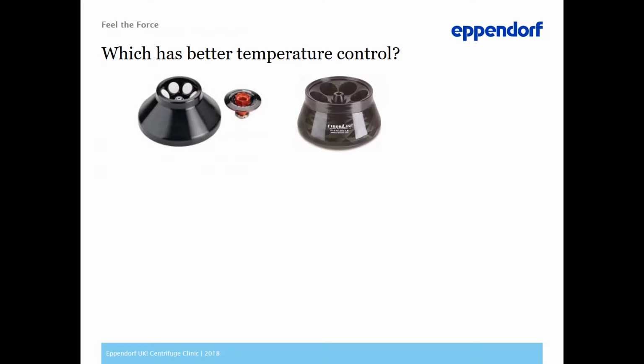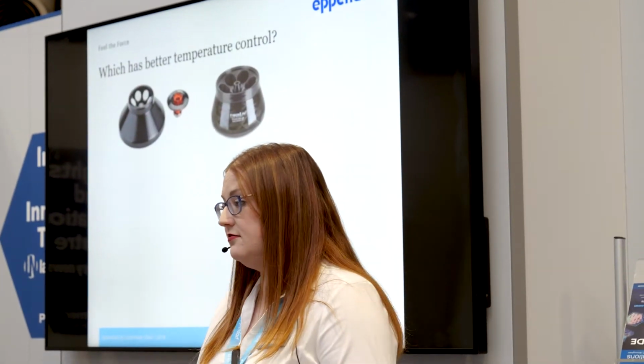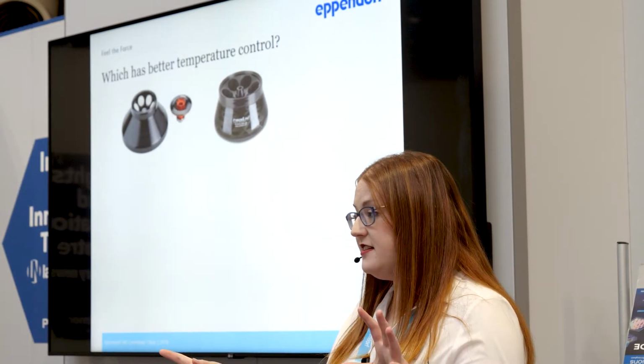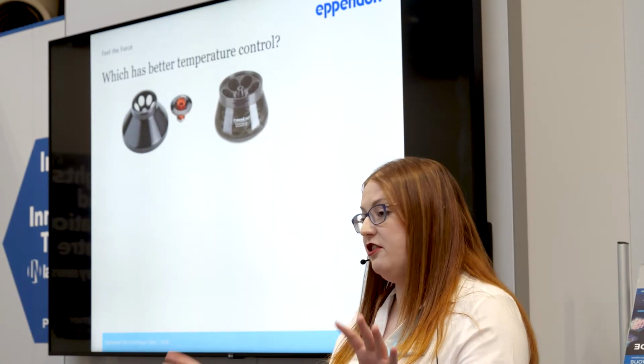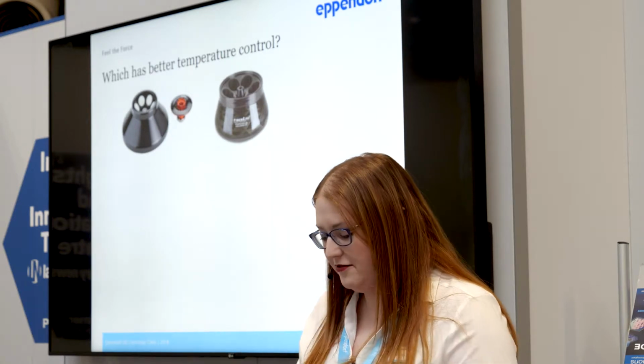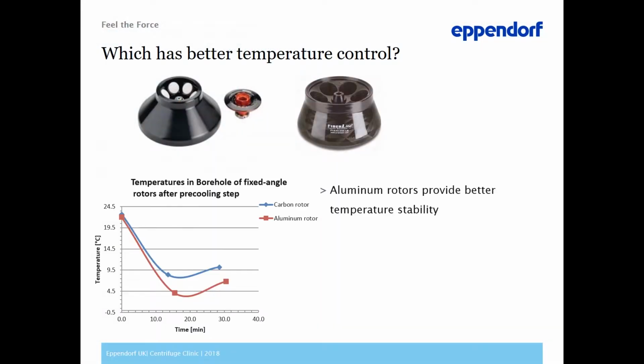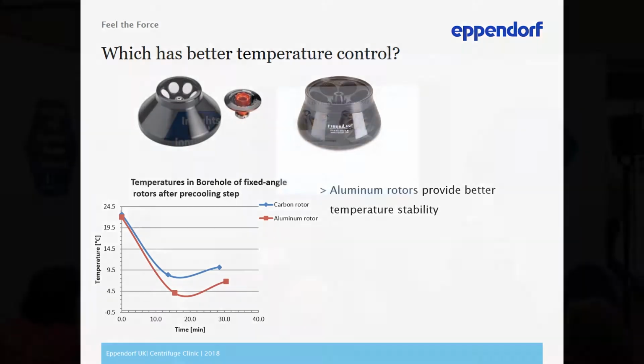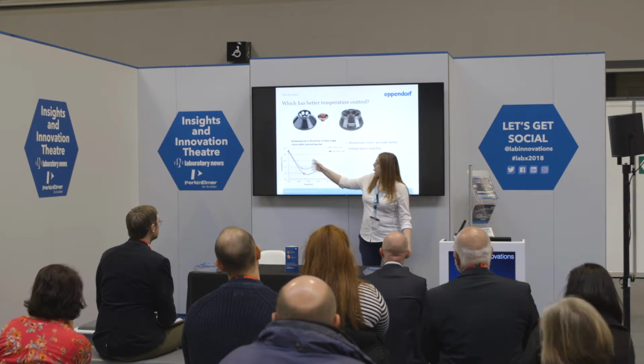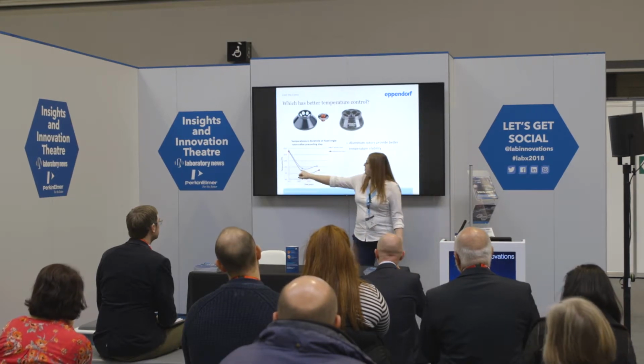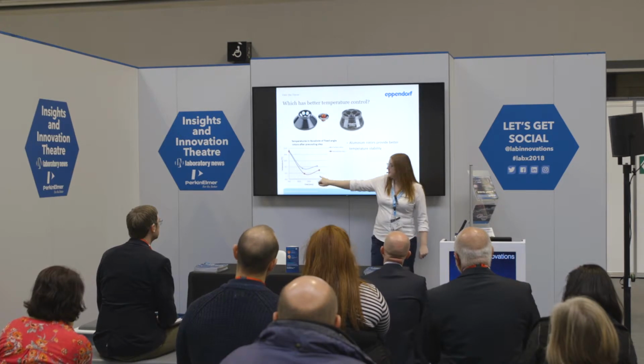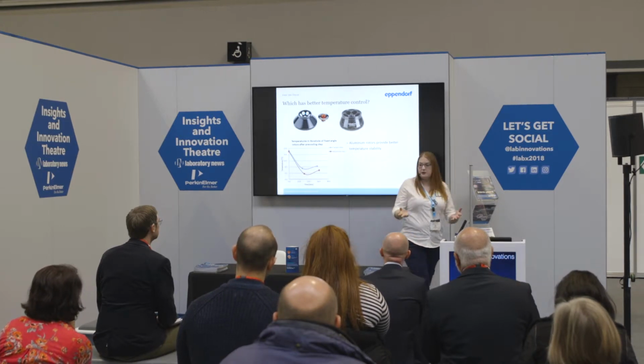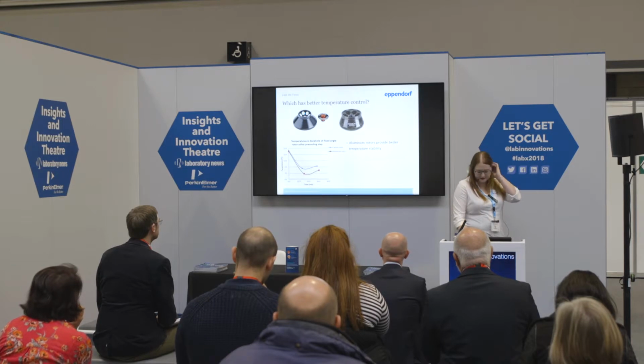So, anyone want to hazard a guess as to whether an aluminium rotor or a carbon fibre rotor has better temperature control? Any guesses? I'm not going to judge you if you get it wrong, so you're better off just guessing. Carbon fibre. You are all wrong! Carbon fibre is an insulator. So, for example, if you stick them in a cold room and cool them down, the carbon fibre rotor never gets as cold as the aluminium rotor, because the aluminium is metal, so it conducts the heat.